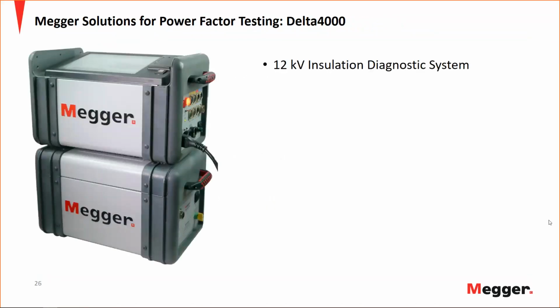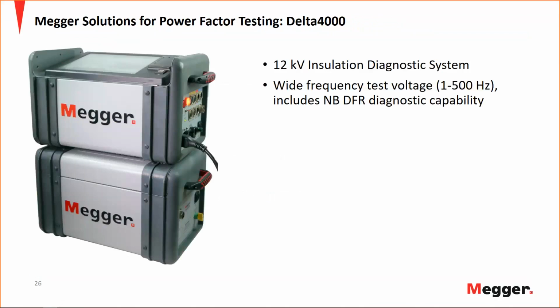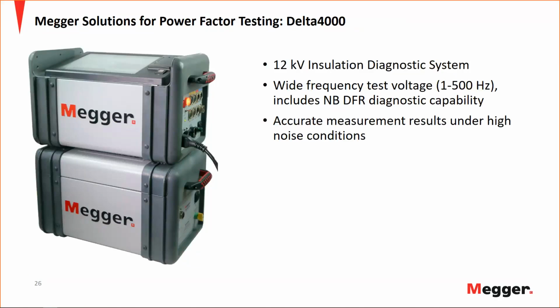And Megger has a couple solutions for doing this. The first is the Delta 4000. This is going to be your standalone 10 kV or 12 kV insulation diagnostic system. We can test from 1 to 500 hertz. You have probably heard us talk about narrowband DFR in the past. This is one step up from 1 hertz diagnostic, but it is there and available for those power users. We can provide accurate measurements in any type of substation or generator, so that way you have the most reliable accuracy possible.